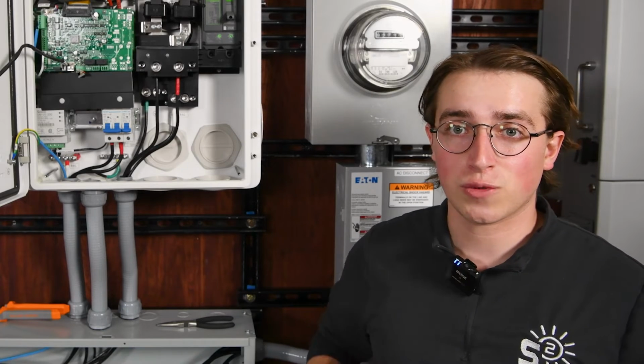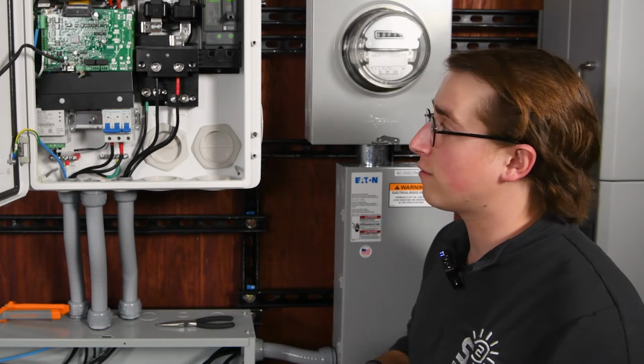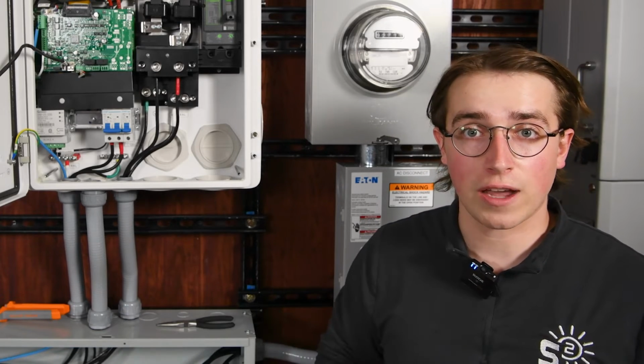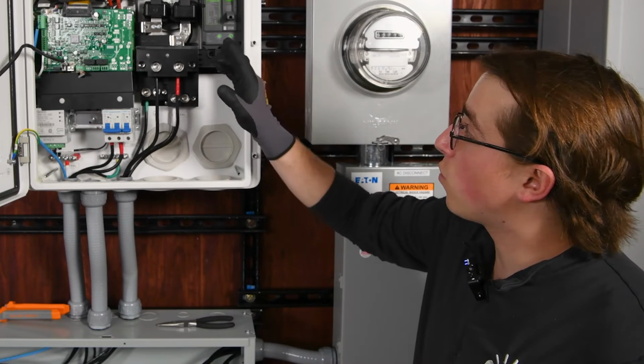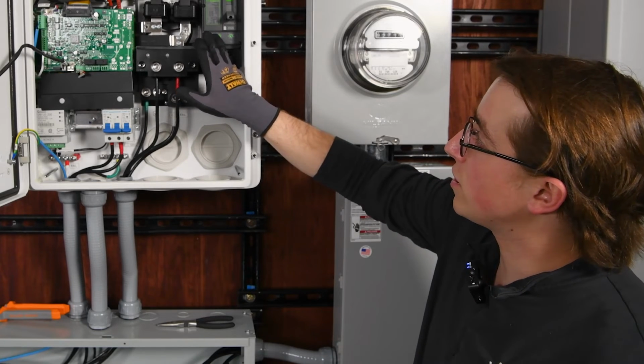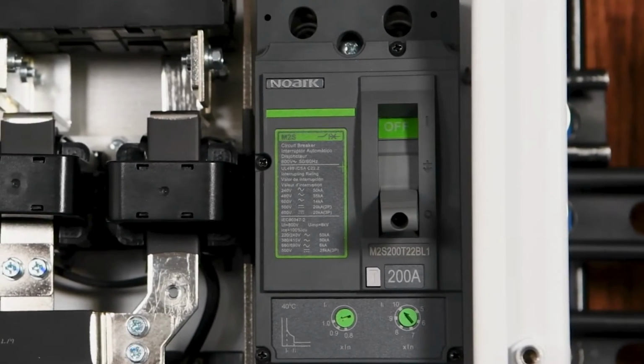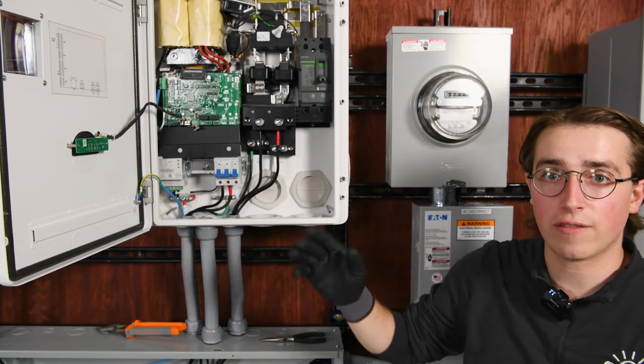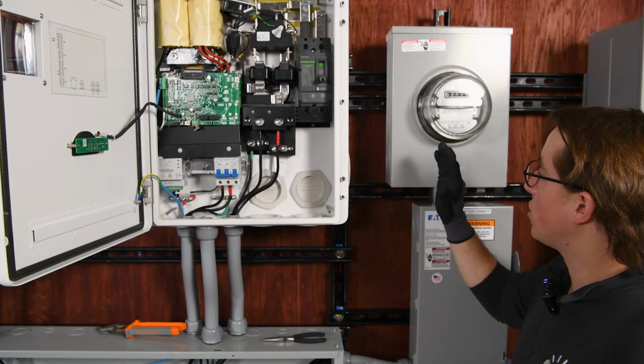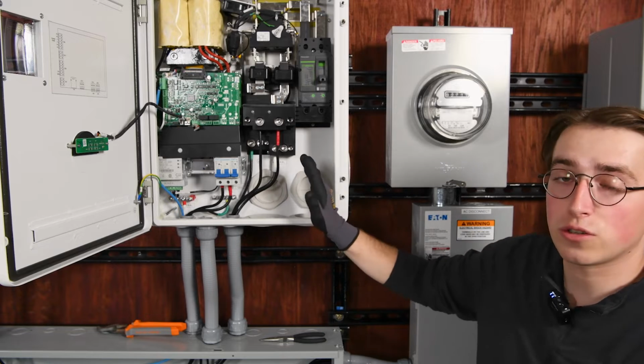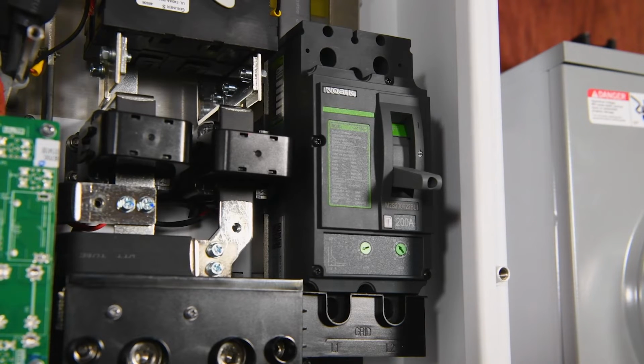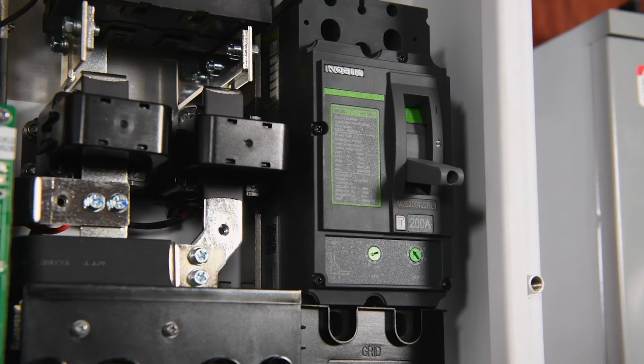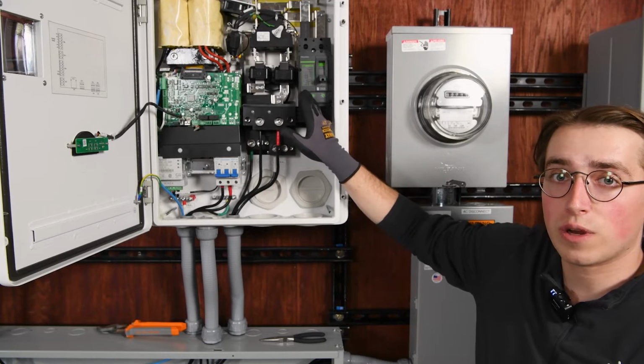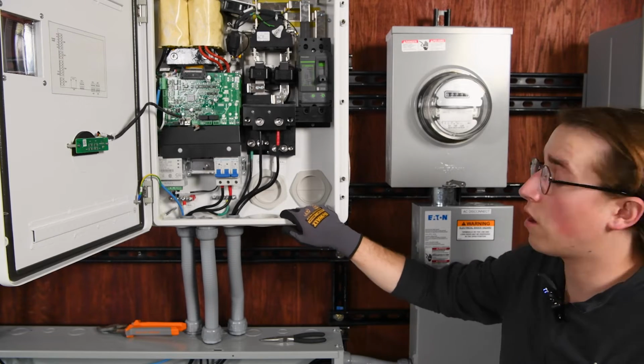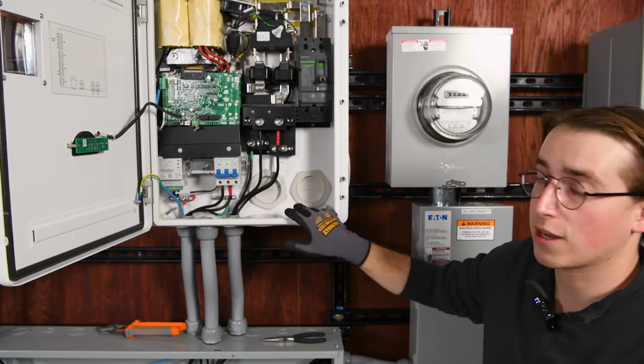When connecting the grid to the SYN, it's important to know what kind of service you have. The most common service that you'll find is 200 amps, which is what the SYN is rated for. As you can see here, it has a 200 amp main breaker, which is the reason that you can use it as your main service entrance, which is when you connect your meter directly to the SYN. If you're running a 200 amp service, you can use the SYN with its 200 amp breaker. Just know that you'll need 3/0 copper wire to make that service entrance connection.